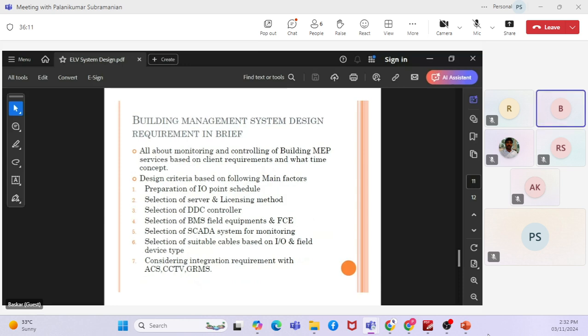First, depending on the specifications, we have to prepare the IO point schedule, which gives each type of system. Let's say we are controlling the booster pump set. What are the controlling and monitoring IO points? And when we are controlling an air handling unit, or a fan coil unit, or the lights, or monitoring the power PMU of the MDB and DBs, depending on that, the IO points have to be derived. It's a weighted criterion that when a person is working on the BMS system, he must know how to prepare the IO point schedule, and choose wisely based on the monitoring and control.